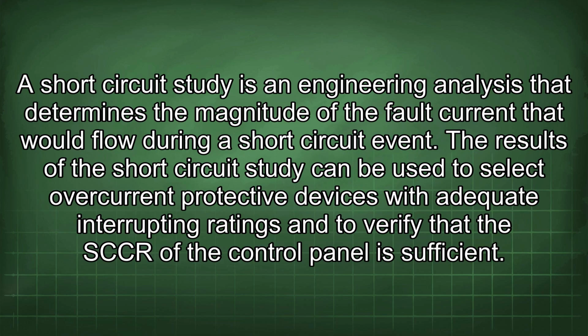A short-circuit study is an engineering analysis that determines the magnitude of the fault current that would flow during a short-circuit event. The results of the short-circuit study can be used to select overcurrent protective devices with adequate interrupting ratings and to verify that the SCCR of the control panel is sufficient.